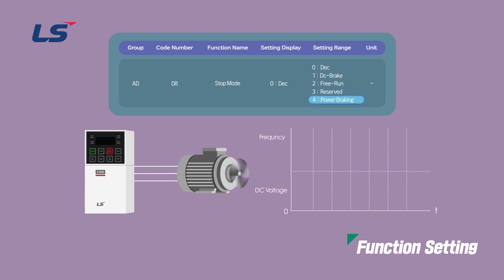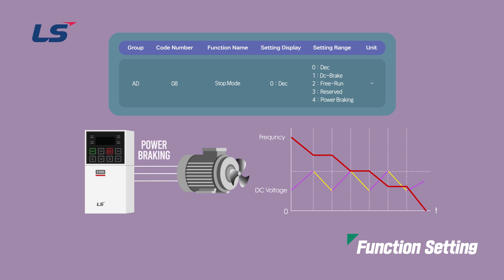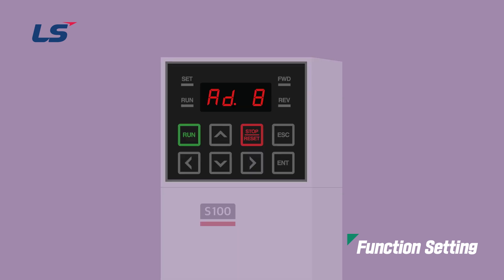The power braking stop method controls the deceleration gradient or re-acceleration to reduce the regenerative energy when the AC drive DC voltage rises above a certain level due to motor regenerative energy. It can be set when a short deceleration time is required without a separate braking resistor and braking unit. Note that the deceleration time may be longer than the set deceleration time, and when used for loads with frequent deceleration, burnout may occur due to motor overheating. To set it, in AD8 stop mode, press enter to display the screen, use the arrow keys to move to 4 power braking, and press enter to complete the setting.